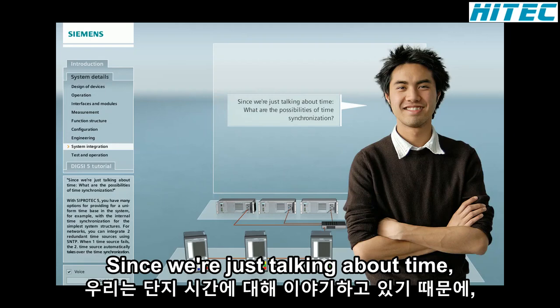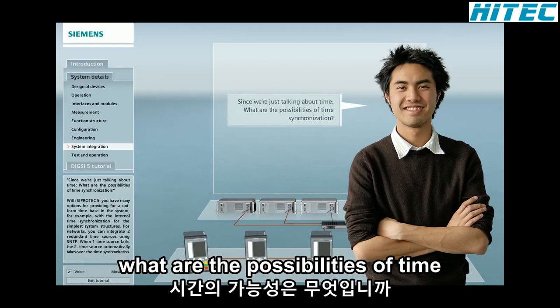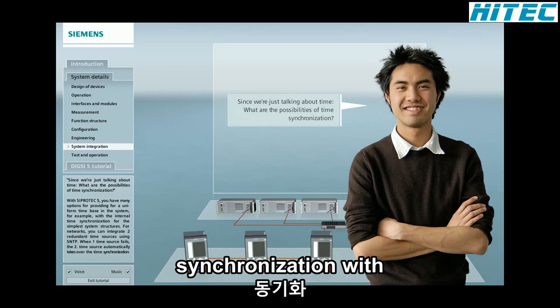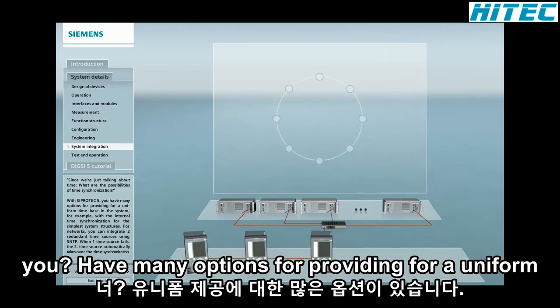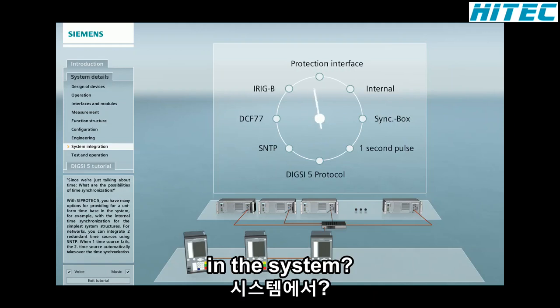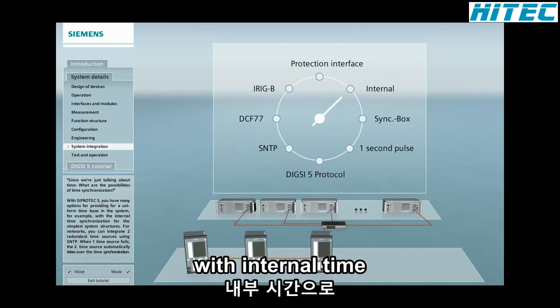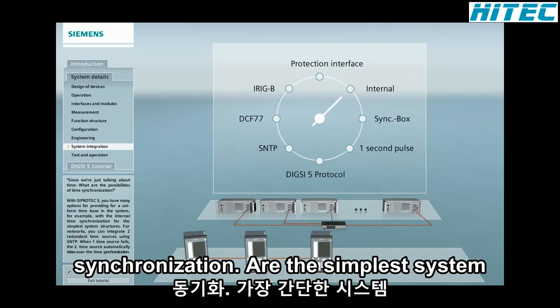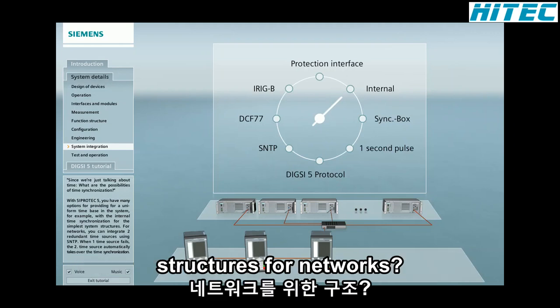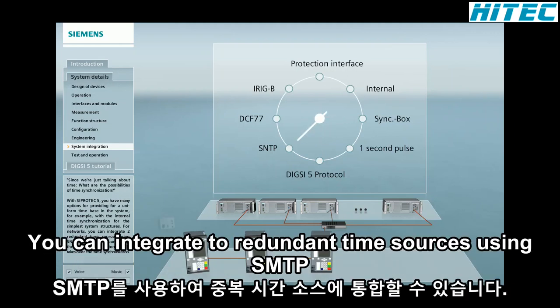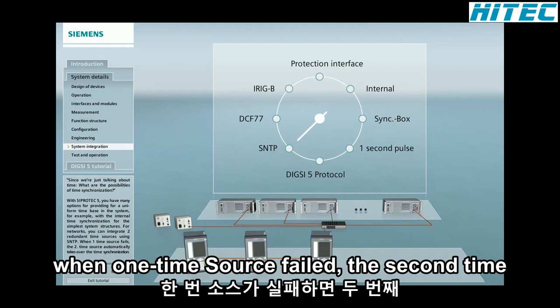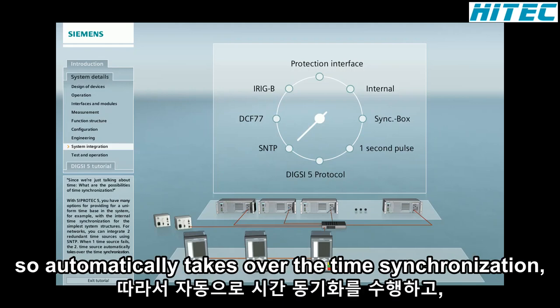Since we're just talking about time, what are the possibilities of time synchronization? With SIPROTEC 5, you have many options for providing for a uniform time base in the system, for example, with the internal time synchronization for the simplest system structures. For networks, you can integrate 2 redundant time sources using SNTP. When one time source fails, the second time source automatically takes over the time synchronization.